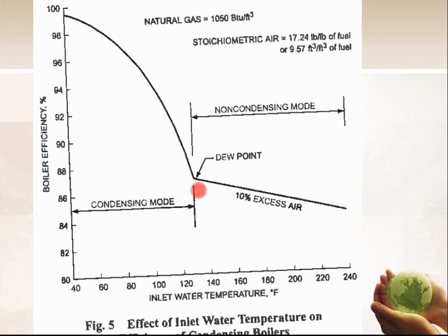As you might know, with regular, non-condensing boilers, you'll see stickers on them that say don't let the return water get below 140 or 150 or something like that, because they don't want to get into condensing mode very often. If they do, the acidic nature of the condensate eats up their heat exchanger. So if you want to have a condensing boiler, you have to have the heat exchanger made out of something that is resistant to that corrosion, a non-ferrous metal, something without iron in it. So you can use stainless steel, you could use aluminum. Those are two very popular ones. You can use some more exotic things like copper nickel, titanium, stuff like that. But pretty much stainless steel and aluminum is what you're going to use.